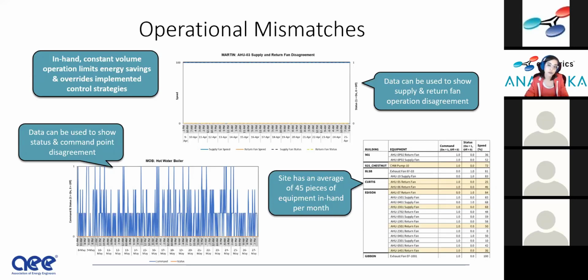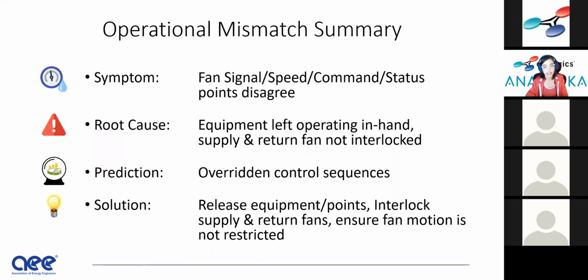Again, you need some sort of analytics to help you parse through this and determine also what are the highest priority units, because you're going to have to put all these on a list and go take them out from being in hand. A lot of times, too, there's savings here. You could be commanding your unit off, but it could be running, and it shouldn't be. So there's significant savings there. Basically a scheduling calculation.